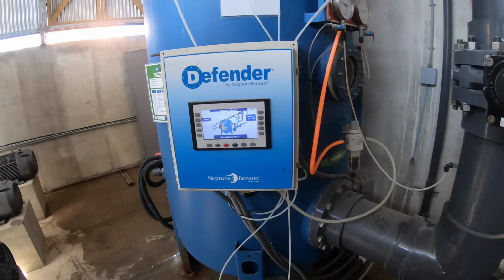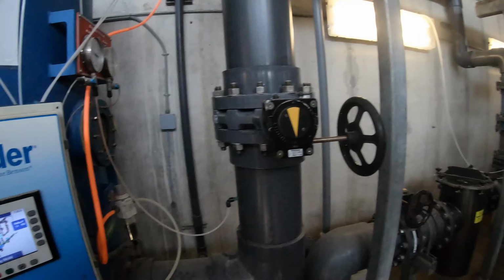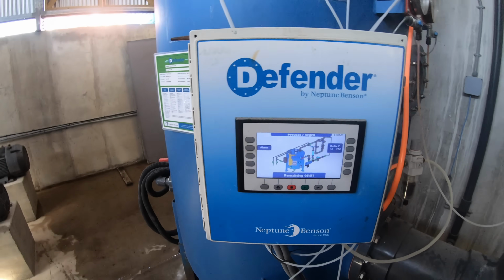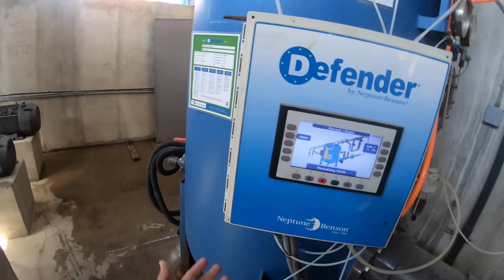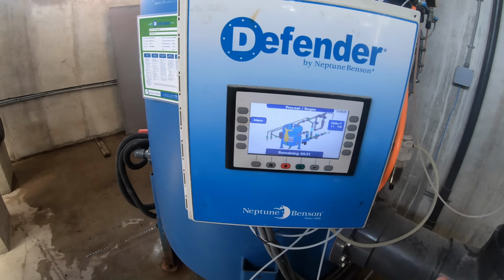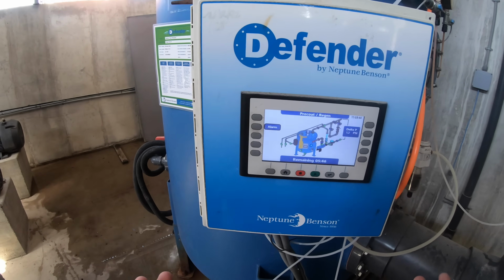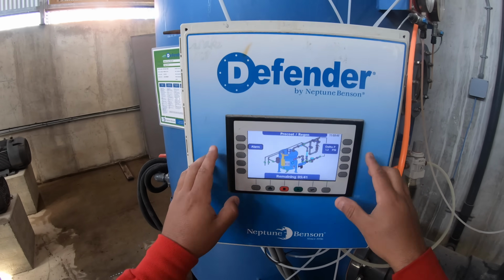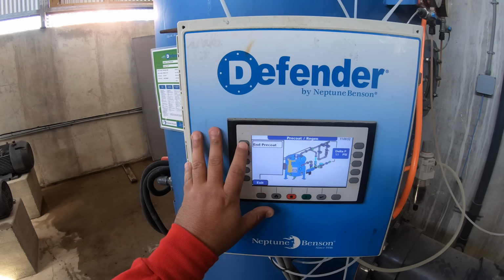So on this filter, if you know what you're doing and you know everything's ready to go and valves and everything are working, you can bypass the pre-coat and get back into regular filter mode, which during the operating day, because we just have so many people in the pools, the less time you have it in bump mode and trying to do this regen, the better for the pool itself. You know, we don't want to stop filtering for a very long time. Very short time as much as possible. So if you have a Defender and you want to do this, it's these two bottom buttons right here. Okay, you click them at the same time, it's going to give you the option to end pre-coat.